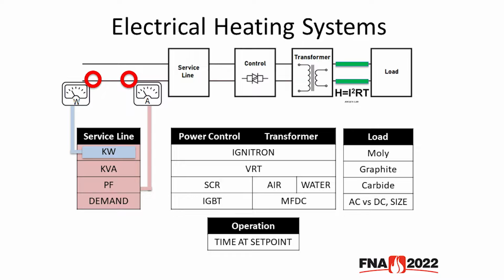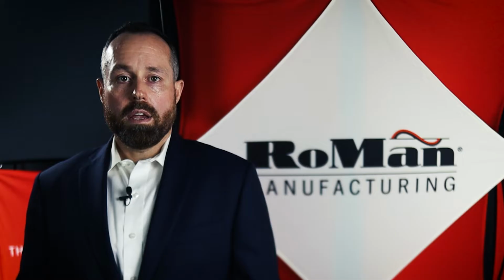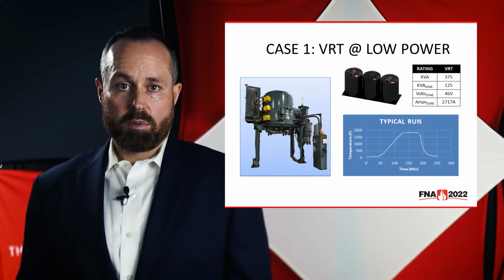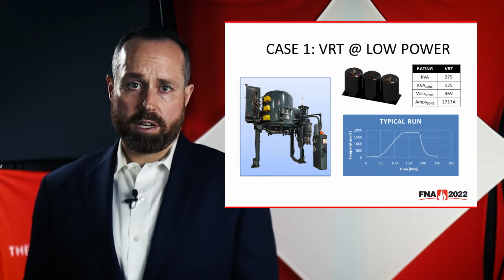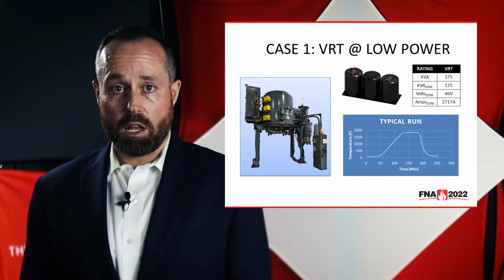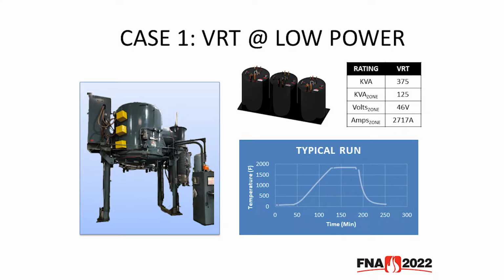In summary, these are the electrical components and variables at play in a typical heating circuit. The next step is to examine the relative efficiencies of these components in practical scenarios. Here's the first example of an electrically underperforming furnace. This case demonstrates why operation of a VRT at low power is electrically inefficient. The furnace is powered with a VRT rated at 375 kVA. This equates to 125 kVA per zone at 46 volts and 2,717 amps.